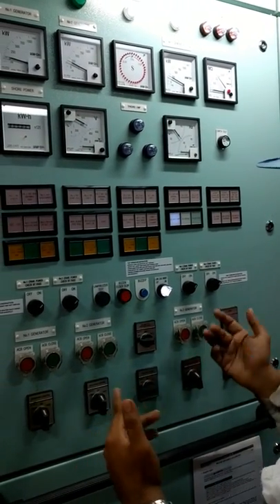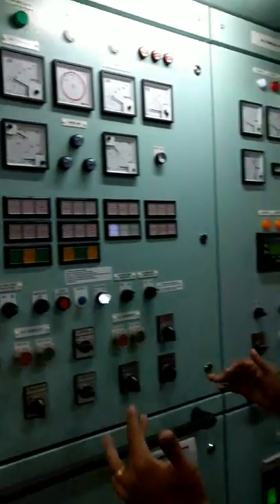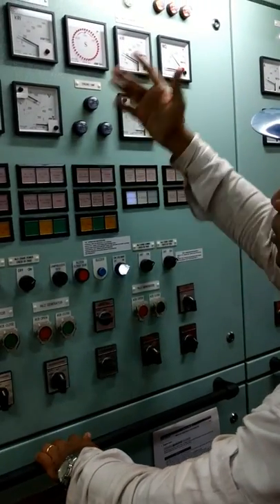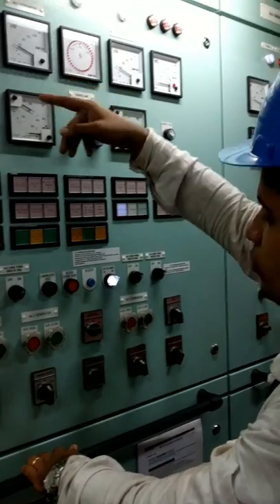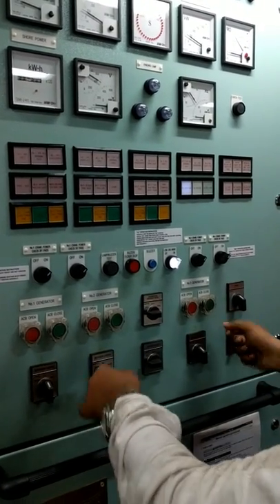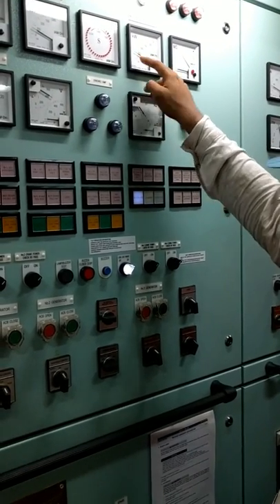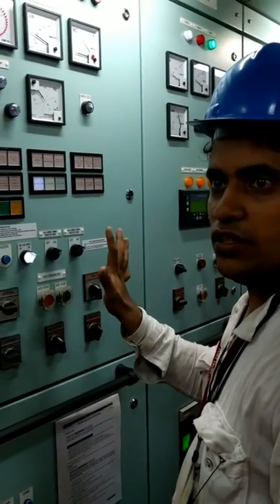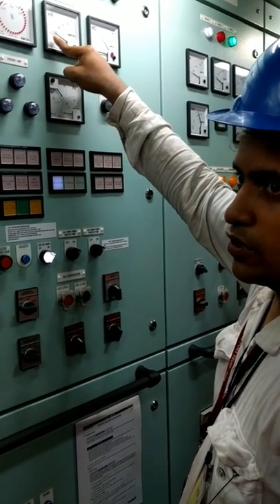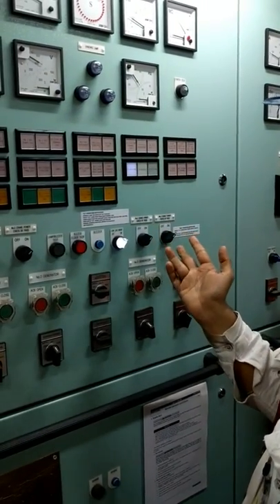If you want to offload a generator — suppose your load requirements are over, load has come down, you have stopped the ballast pump, and now you want to stop number three — you do the reverse. You raise number two and lower number three together, until number three reaches around 20–30 kW. When you reach 20–30 kW, press ACB open on number three only. The 20–30 kW load will shift to number two, then you can put it in auto.